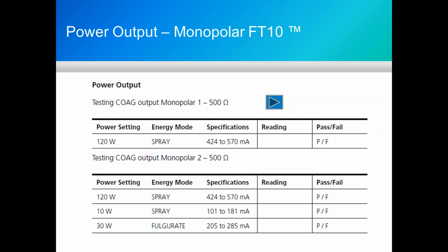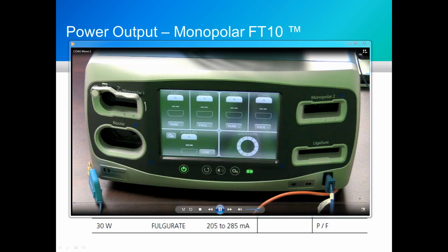And then you see the second half of that slide talks about how you would do your testing on Monopolar 2 for coag. So we do a couple of different settings. We do 2 at spray at the minimum wattage, at the maximum wattage, and at fulgurate. So let's see what actually happens here.